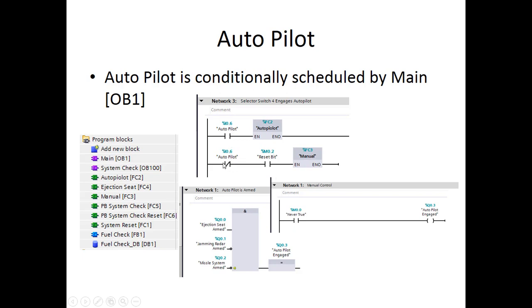Because if this switch was true and we didn't have the reset bit, it was automatically going to do the manual, and it was automatically going to turn the light off. And what happened was, when we cycled the lights, only 4 of them came on, because the 5th one came on, but it was only for one scan, and we couldn't see it because immediately manual ran, which turned it off. We put the reset bit in there, and then we said don't run the manual until we've pushed the button and turned all the 5 lights off.